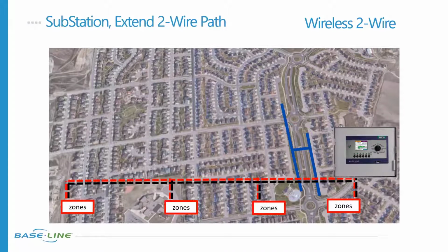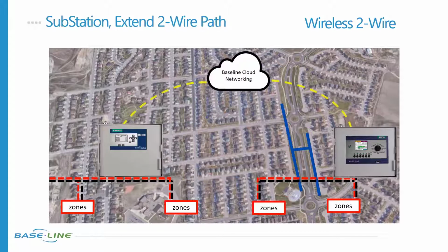There was a contractor I heard of with a new installation that had run the wire too long, even though it was designed properly—probably due to how they had to route it, and it was really going to hurt them. We had a solution: they separated it into 2 wire segments and connected them virtually, electronically, through substation and baseline cloud networking. This definitely extended the reach of the 2-wire system—instead of 5,000 or 8,000 feet, they could now go 16,000 or 20,000 feet of wire.